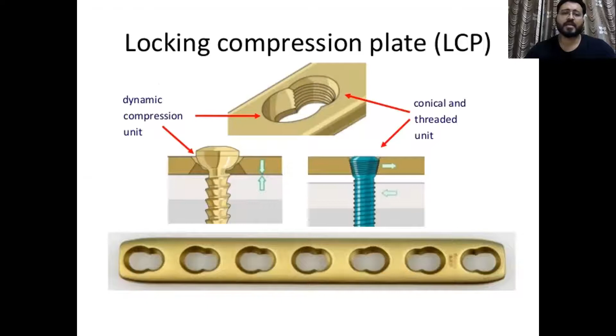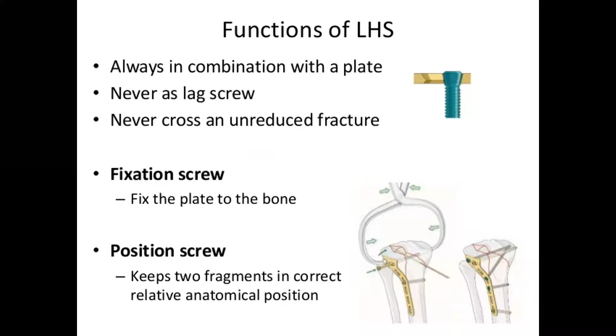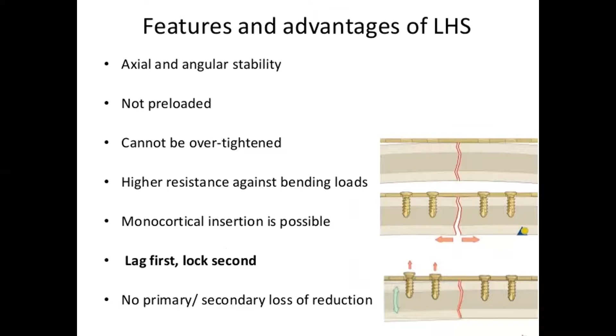Then function of the locking head screw: always in combination with the plate, never as a lag screw, never crossing an unreduced fracture. Fixation screw fixes the plate to the bone. Position screw keeps 2 fragments in the correct relative anatomical position. Features and advantages of the locking head screw: axial and angular stability, not preloaded, cannot be over-tightened, higher resistance against the bending load. Lag first, lock second, there is no primary or secondary loss of reduction.